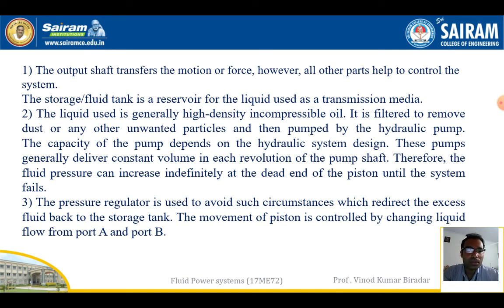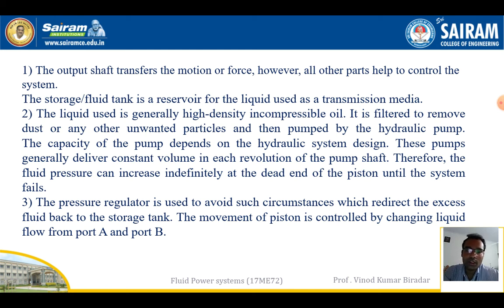These pumps generally deliver a constant volume with each revolution of the pump shaft. Therefore, the fluid pressure can increase or decrease at the normal stage. The pressure regulator is used to avoid excess pressure, redirecting excess fluid back to the storage tank. The movement of the piston is controlled by changing the liquid flow from port A to port B.